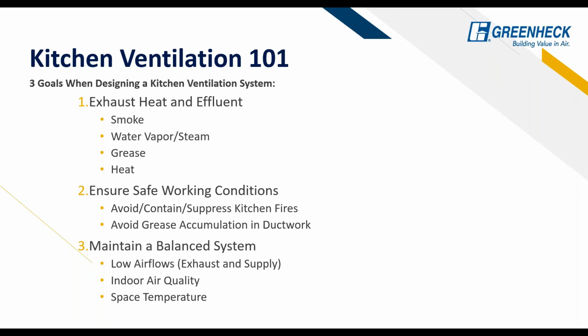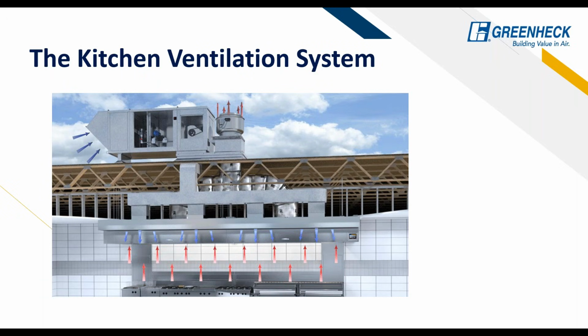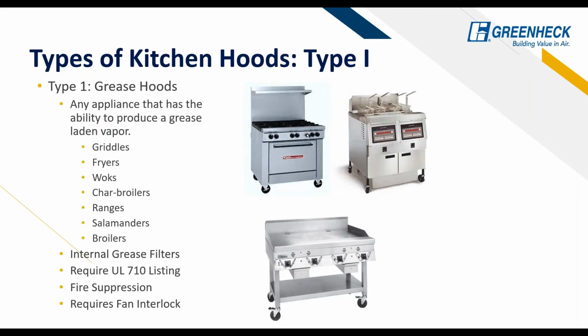entire space there. So this is a typical setup where you'd have your hood over some appliances, exhausting up to a dedicated exhaust fan, and then you can have a dedicated makeup air fan delivering makeup air either right at the hood in a supply plenum, almost creating like an air curtain, or we can also just disperse this air throughout the space and makeup air that way.